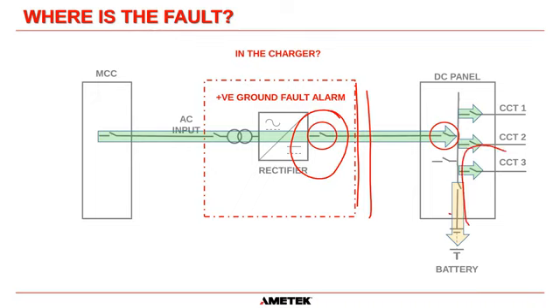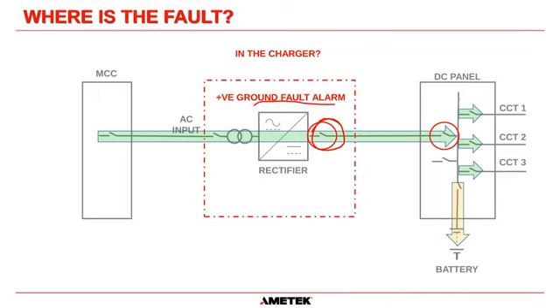The battery will maintain your loads, so you're only going to do it for a short period of time. Make sure your battery is available and capable of providing the load. But you can open this breaker, and if the ground fault alarm stays on, then yes, something inside the charger has gone to ground. That is extremely unlikely. It's very, very unusual that the ground fault is actually in the charger.